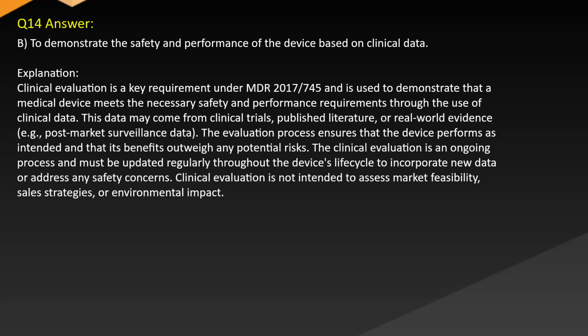Explanation. Clinical evaluation is a key requirement under MDR 2017-745 and is used to demonstrate that a medical device meets the necessary safety and performance requirements through the use of clinical data. This data may come from clinical trials, published literature, or real-world evidence, e.g., post-market surveillance data. The evaluation process ensures that the device performs as intended and that its benefits outweigh any potential risks. The clinical evaluation is an ongoing process and must be updated regularly throughout the device's lifecycle to incorporate new data or address any safety concerns. Clinical evaluation is not intended to assess market feasibility, sales strategies, or environmental impact.